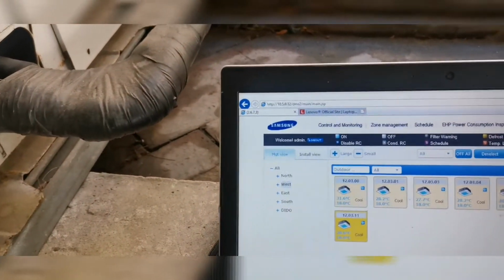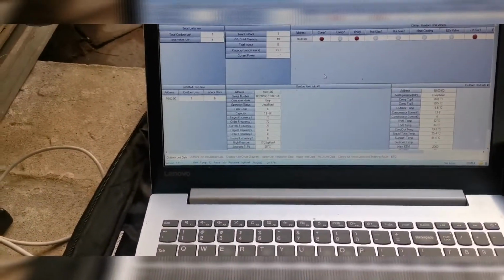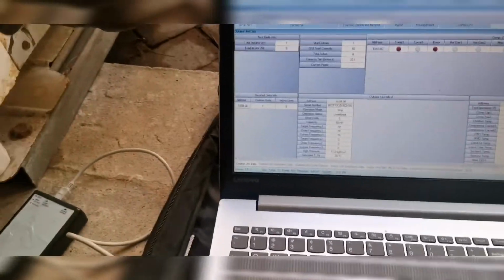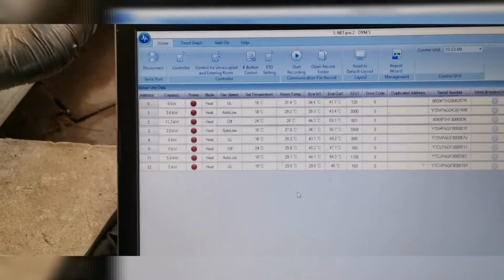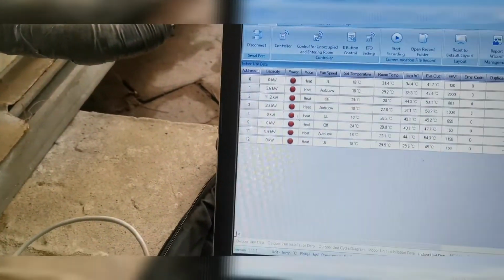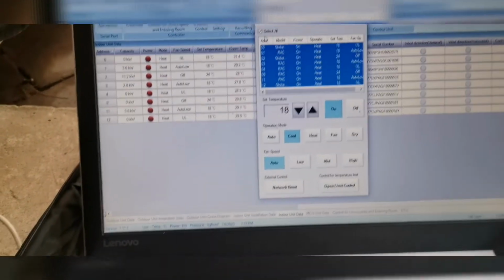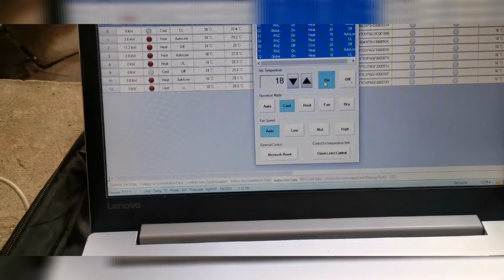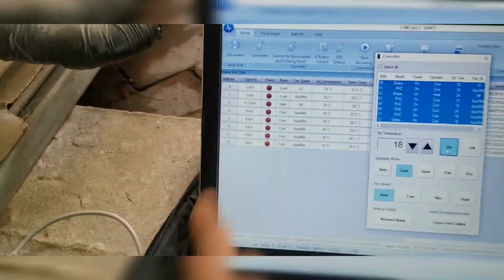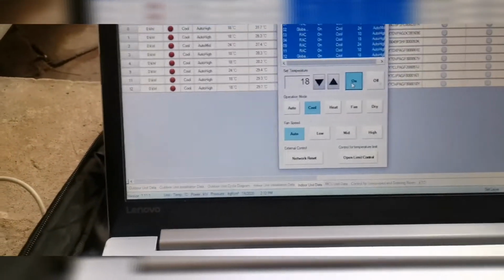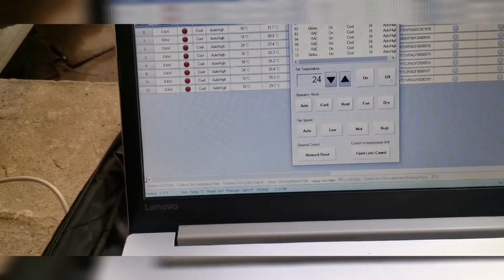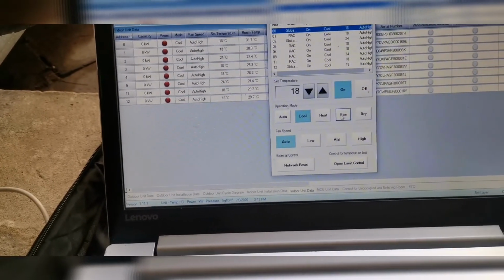As you can see, I'm in my Internet Explorer, but if I scroll down and over here, this is my service checker right here. So you can see the operation mode stopped. Firstly I'm going to go to indoor unit data, and I can see everything has stopped. Indoor units are still on though, so we'll go to control, select all, cool, and press on, and there, as you can see, everything is starting to change from a heat to a cool mode. Then I'll say unselect, and that one specifically I'll put on fan only.